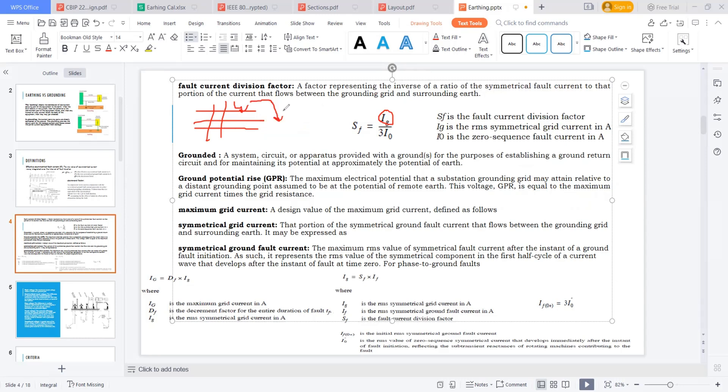But what is the maximum current? Suppose 25 kiloamps is the fault current occurring in my system. On the grid, I can see only 12.5 kiloamps flowing in the grid, the remainder going to the surrounding earth. Then the fault current division factor is 12.5 divided by 25, which is nearly 50 percent. So 0.5 is the fault current division factor.